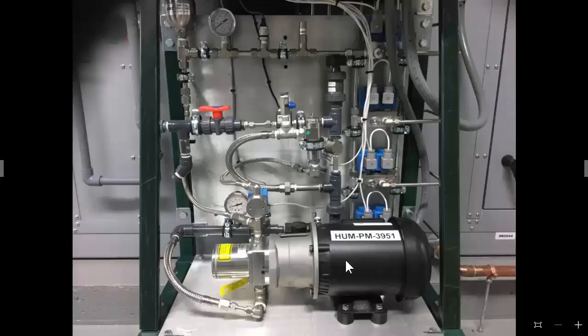It is a variable speed pump that at times regulates the output pressure and at times is bypassed through the bypass regulator. There are a lot more valves involved that could cause different scenarios. And we have the dump portion of the high pressure side, the line that actually dumps high pressure water to drain when each one of these zones shuts off.